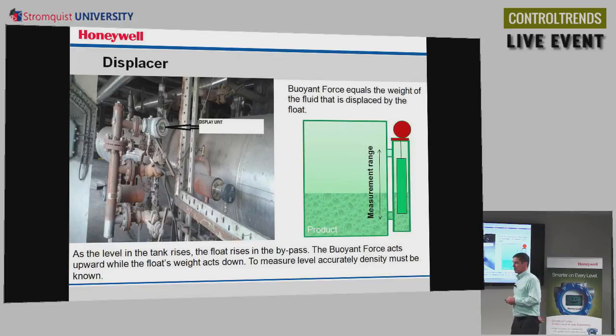Displacer, this is another measurement. We talked a little bit about this earlier this morning, but what we're doing is using a bypass. Almost all the time, not all the time, but almost all the time, displacers will be mounted in a bypass. And the level in the bypass is going to be the same level as in the tank. We're making that measurement there. And that's a good way to isolate the measurement from any sort of turbulence or disturbances in the tank.